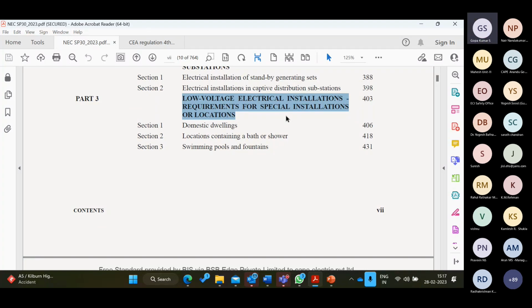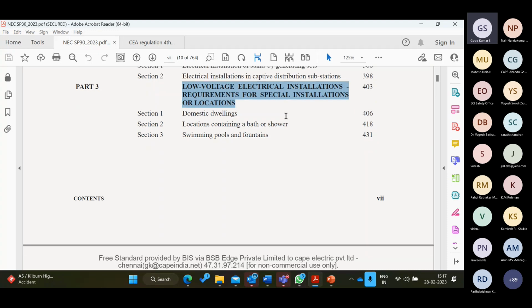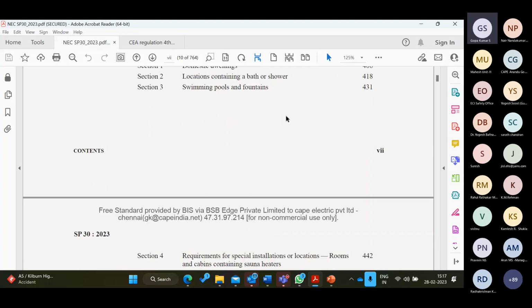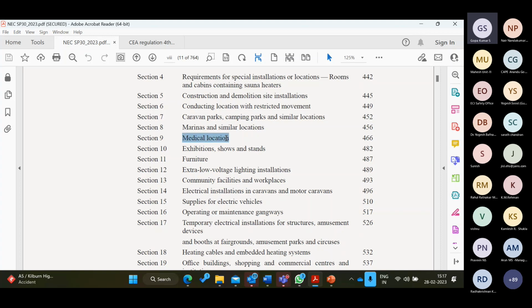Every application may have something special. For example, residential purpose, something special. Swimming pools and fountains, something special. Medical locations, something special, in the sense that these are additional safety measures. So part 1 is applicable and part 3 is applicable over and above part 1. While reading part 1 and part 3, you have to be very careful, because part 3 sometimes explains that clause number XXX of part 1 section 13 is not applicable, or it has to be read in a different way. So some simple explanations are there.